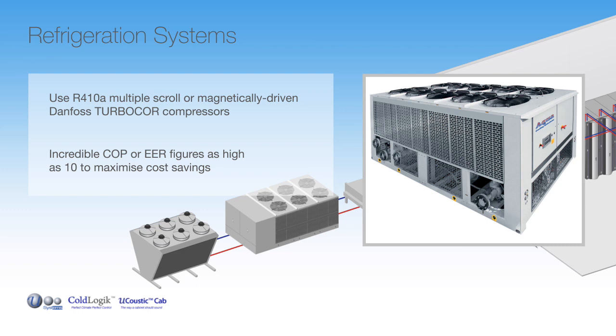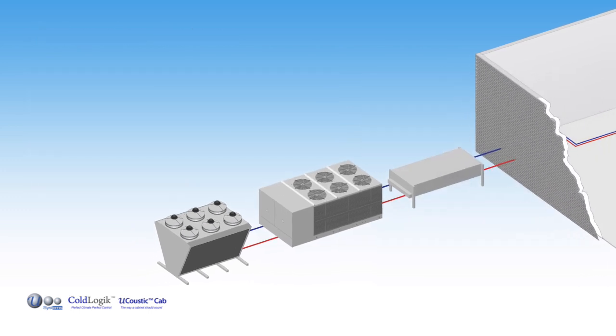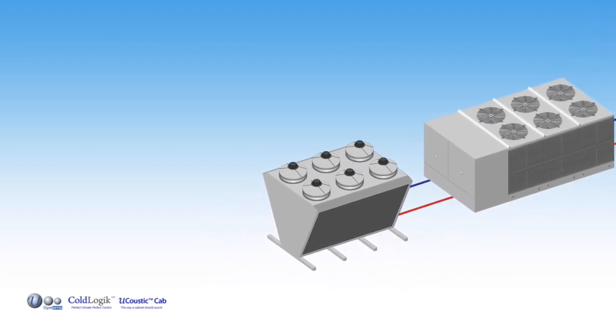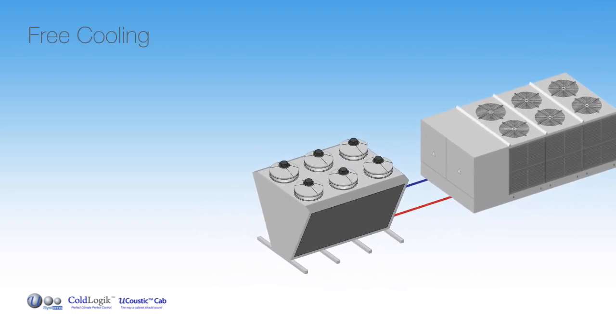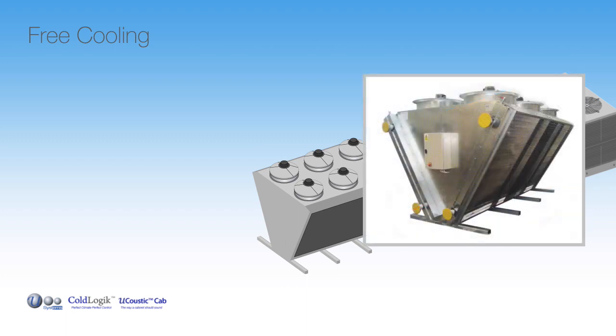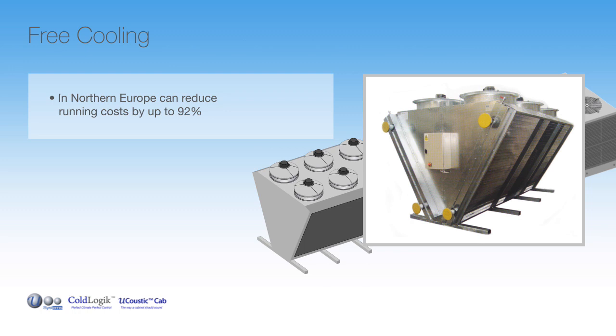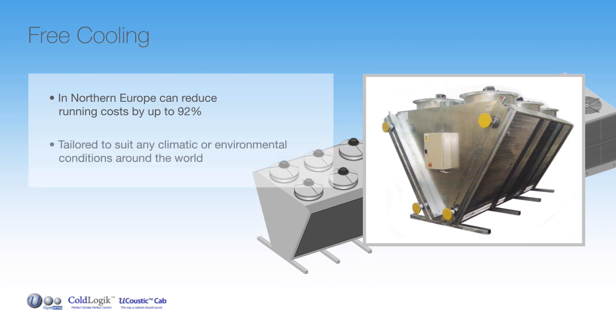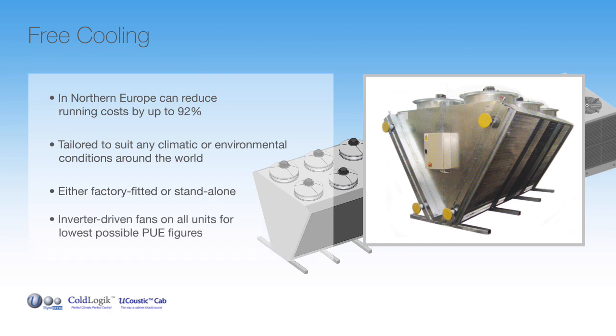In order to capitalize on the efficiency of ColdLogik, it is imperative to use, where possible, free cooling. It plays a significant part in energy cost reduction and, in practice, using free cooling in Northern Europe can reduce the running costs of the refrigeration system by up to 92%. Our unique systems are tailored to suit any climatic or environmental conditions around the world. The free cooling modules can either be factory fitted or stand alone depending on the site requirements, and with inverter-driven fans on all units, they ensure that PUE figures are as low as possible.